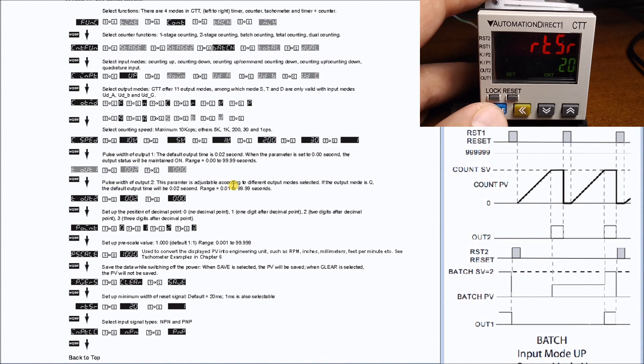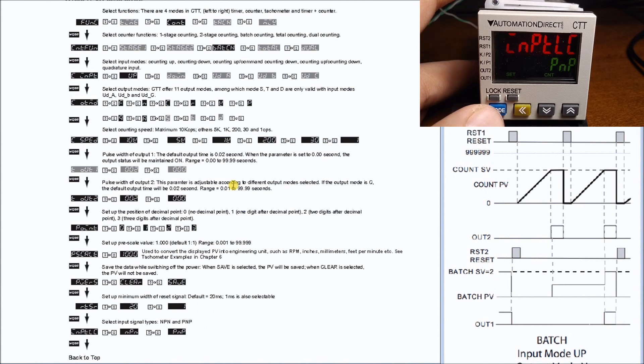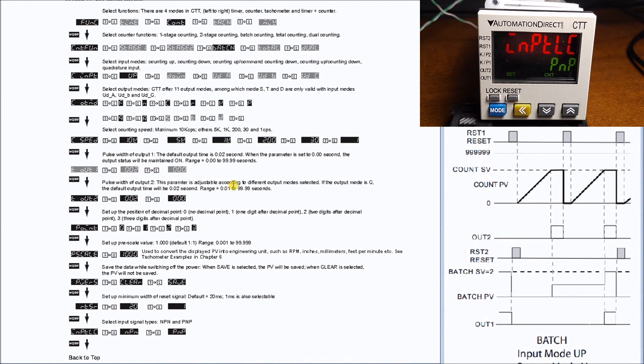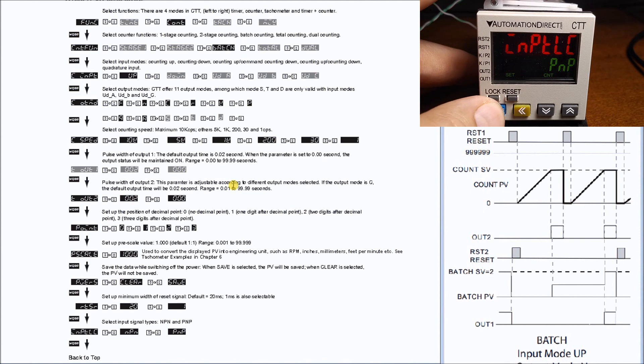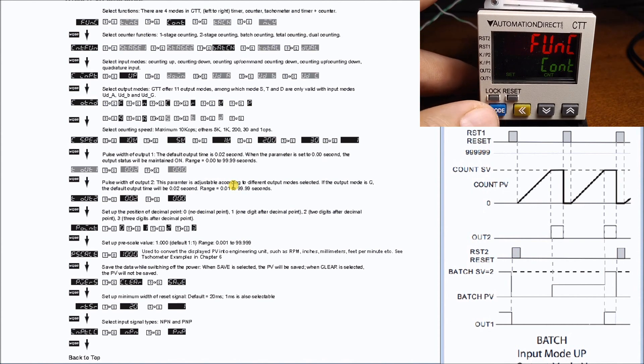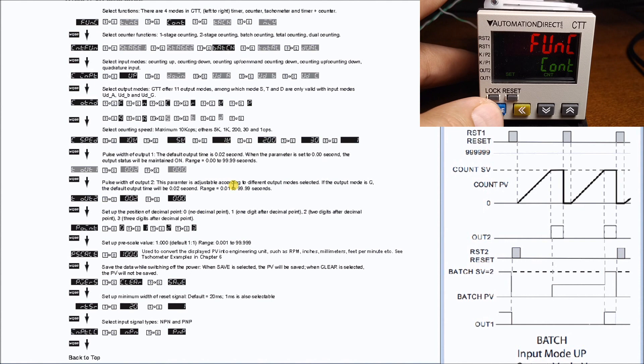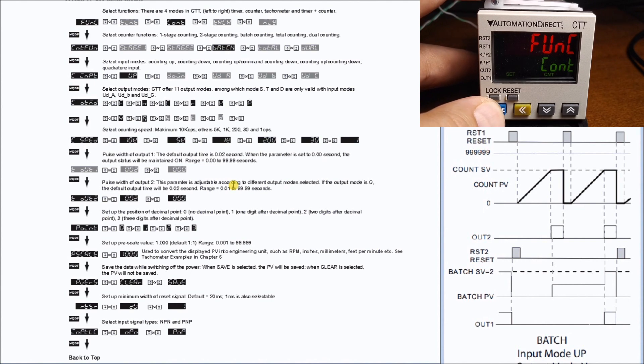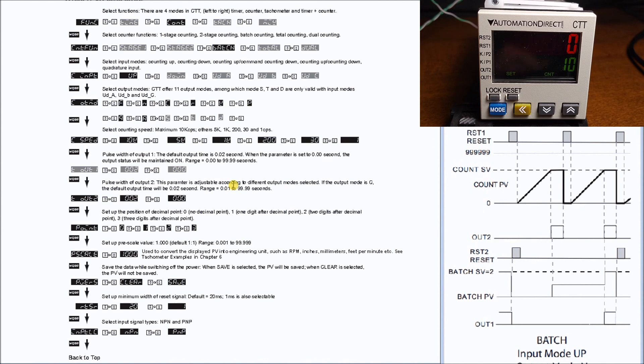Hitting mode again is our reset which is set for 20 milliseconds. Then we have our input type which is PNP, which goes back to the way in which the unit is actually wired in. Mode once again takes us back to our start which is our count feature. Hitting mode and holding for three seconds will take us back into our run mode, and what you'll notice is that we actually have a count set for 10 here.